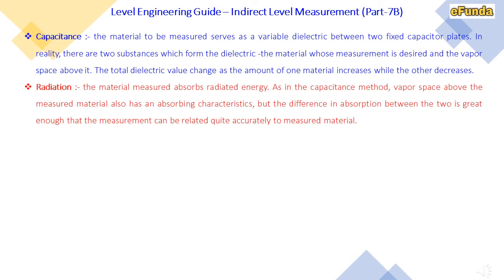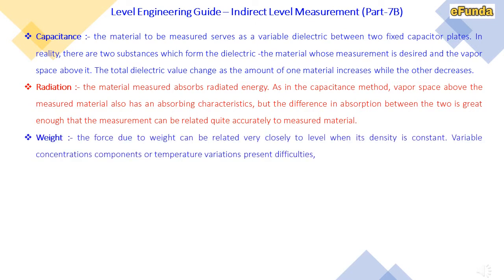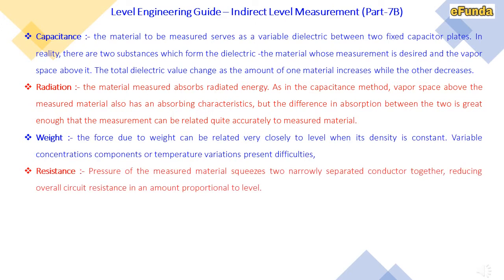Radiation: the measured material absorbs the radiation energy. Similar to the capacitance method, the vapour space above the measured material also has absorbing characteristics, but the difference in absorption between the two is great enough that the measurement can be related quite accurately to the measured material. Weight: the force due to weight can be related closely to level when density is constant, though variable concentration or temperature variations present difficulties. Resistance: the pressure of the measured material squeezes two narrowly separated conductors together, reducing the overall circuit resistance in an amount proportional to the level.